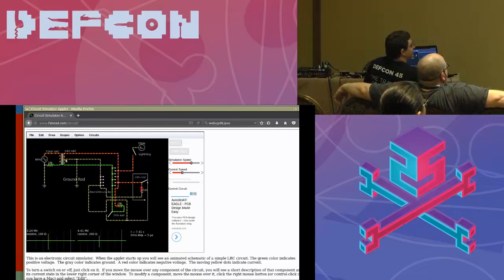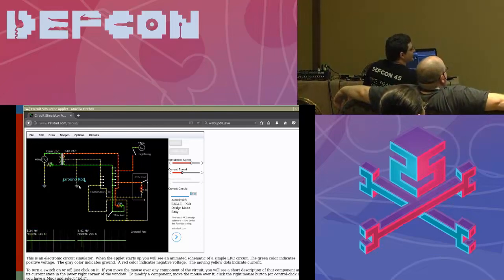So the ground rod is basically the least important part of your grounding system. This neutral ground bar is what handles fault currents — it's what's handling all of that sort of thing.